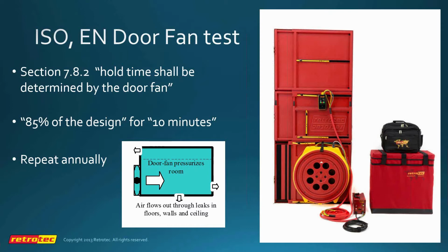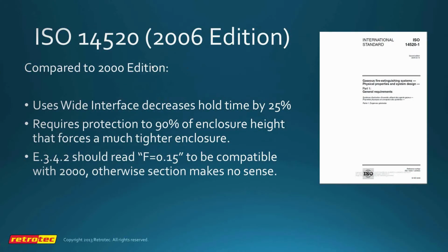Both standards require that the hold time, the concentration is held at 85% design for 10 minutes, and there are sections in there that ask that the test be repeated annually. On the next slide here, we're talking about the 2006 version of ISO, which was the first time that some major changes have been made.